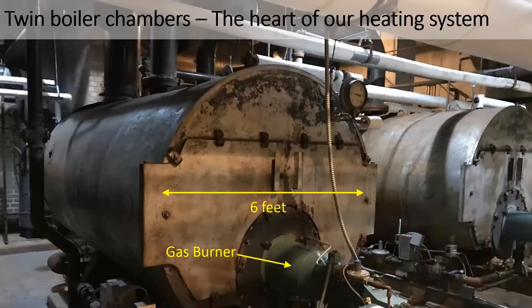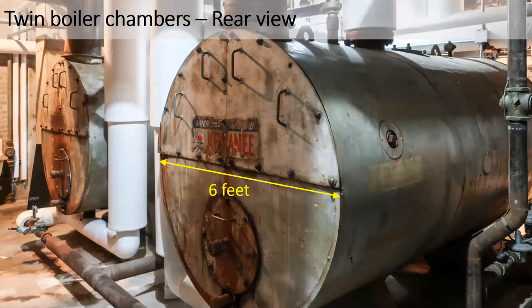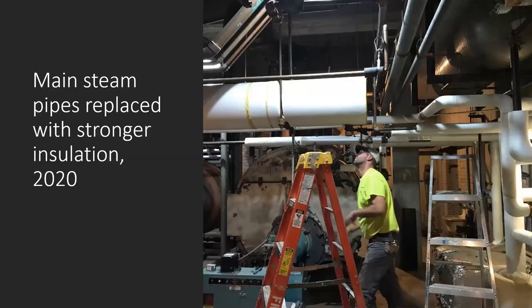A major renovation or replacement is estimated to cost about $700,000. However, according to our consultants, the two parallel boilers provide both redundancy and extend the time likely for repairs. While old, these boilers can be continuously repaired more or less indefinitely. However, the heat distribution system did offer efficiency improvements and opportunities.